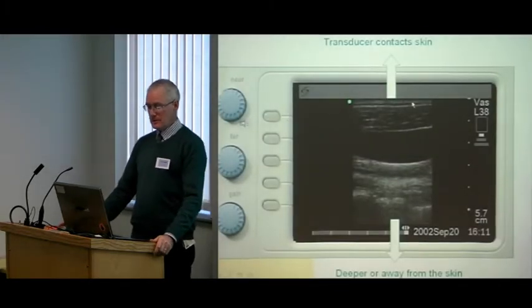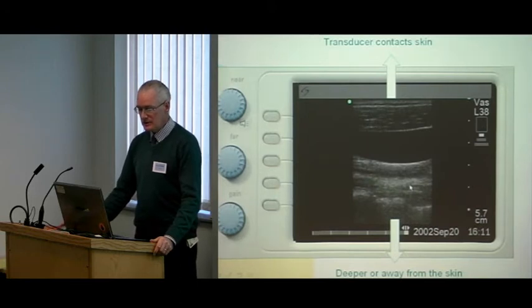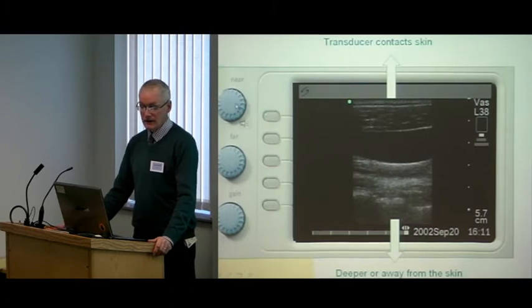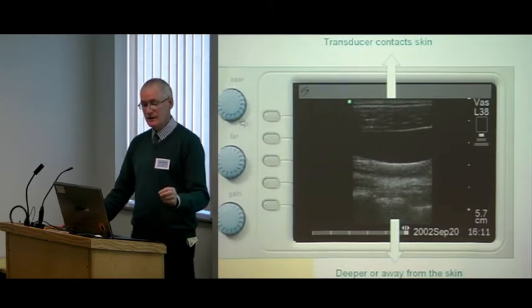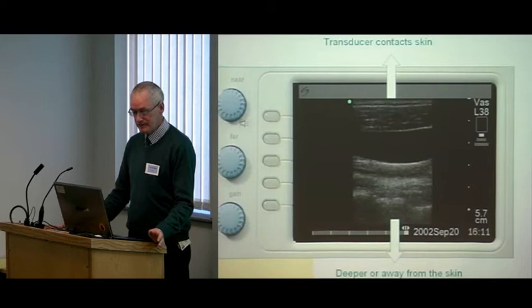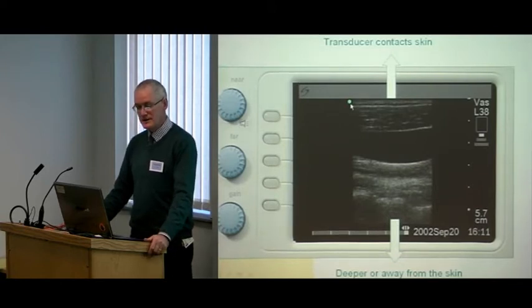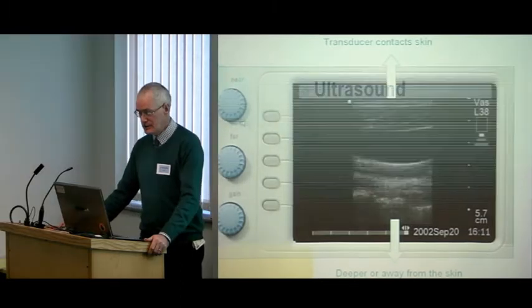So this is one of the most simple machines that you could possibly see. We do have some in the department still, and here we have a brightness button which is called the gain control. You can increase the brightness for the near field here in the superficial part of the image, and the brightness for the deeper part of the field here in the more remote parts of the body. That's the gain control. Okay, so that's brightness. There's the actual plastic probe marker, which is always to the right side for a transverse image, and for a sagittal image, that's the head end. That's the normal orientation.